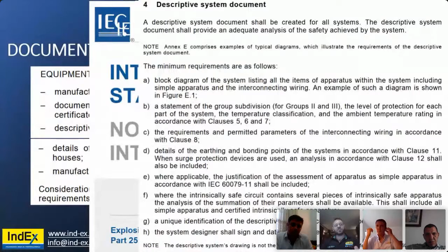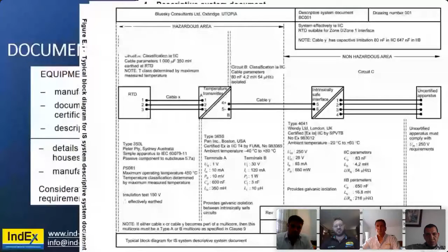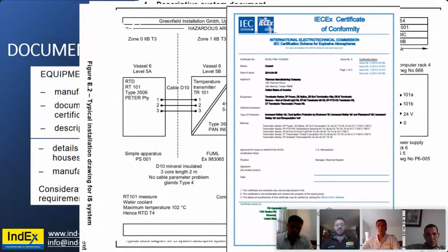So in that standard, it will talk about systems. When you think of intrinsically safe to -11, that's just one of the pieces of equipment. Intrinsically safe is from the barrier, the cables, junction boxes, the equipment at the end, and any other equipment that is part of that loop. So that descriptive system document describes all the requirements, and the IEC standards give you the calculator and the format and layout for the possibility to define your hazardous areas, such as in this format. Gives you layout, gives you cable schedule, terminations, makes it very easy. And once again, you have your individual IECEx certificates for the individual pieces of equipment.